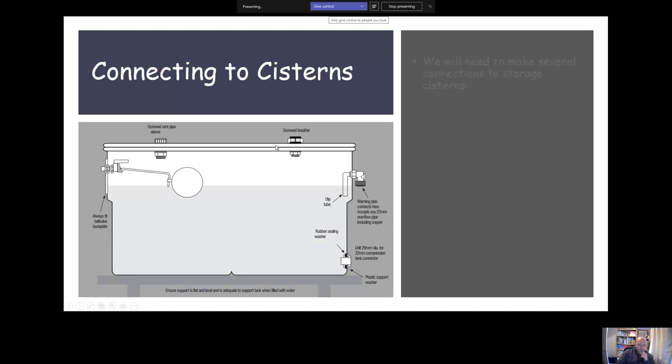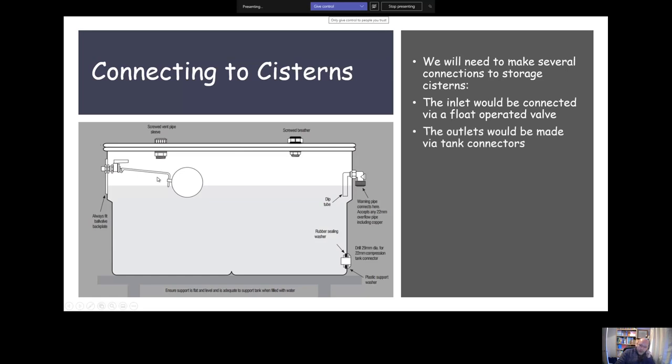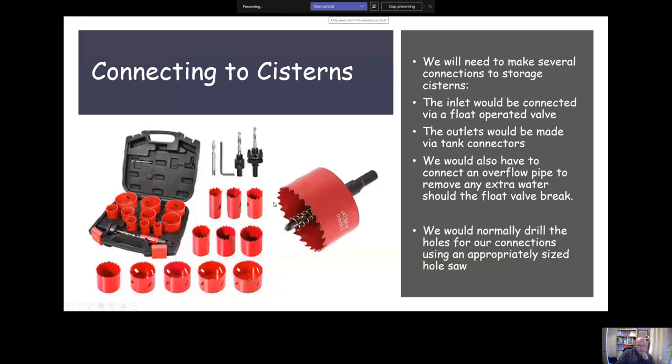For our connections connected to cisterns, there's lots of different connections we're going to need to make. Generally like I've already said, our inlet would be connected by a float operated valve and the outlets would be made with tank connectors. The overflow would be connected as well to remove any extra water should the float valve fail. We would make our connections using a hole saw. We need to make a correct sized hole using a hole saw, always make them just a tiny little bit bigger than the thing that needs to go through.